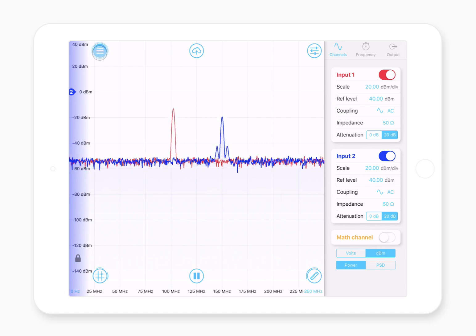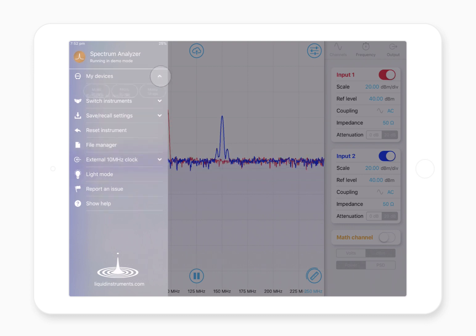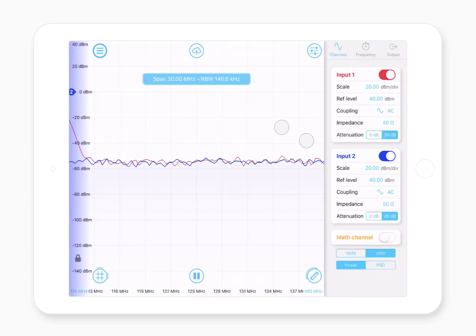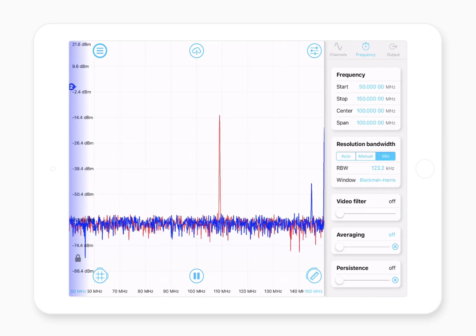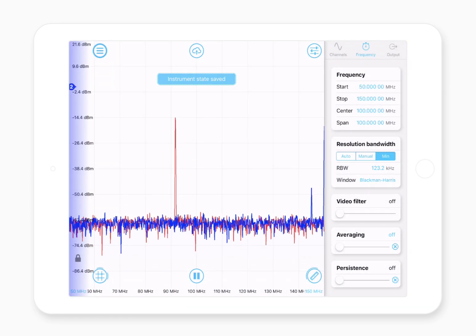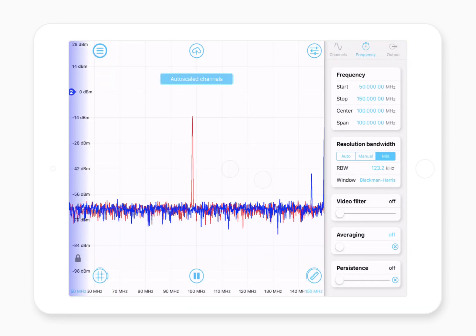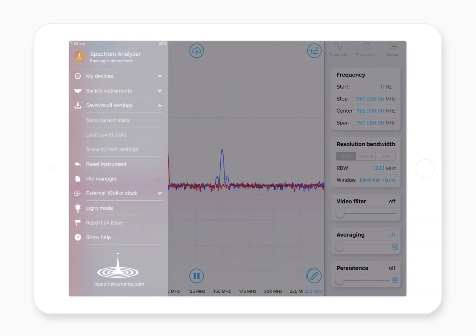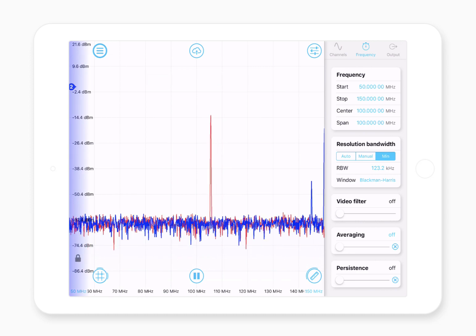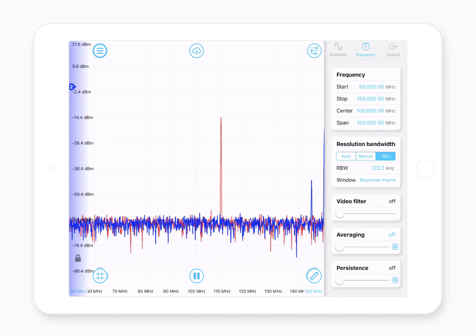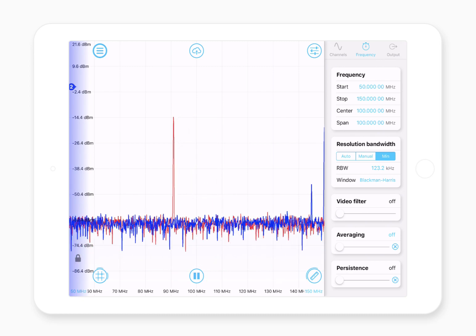Up the top left we have the main menu button — this allows you to select different devices, select instruments, and save and recall settings. If you get some different settings applied, you can save that current state, and then if you want to go back to it later, loading that saved state will bring you back to that exact configuration. That can be handy if you want to quickly snap back to a very specific, predetermined instrument configuration.